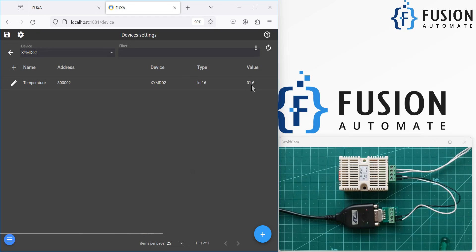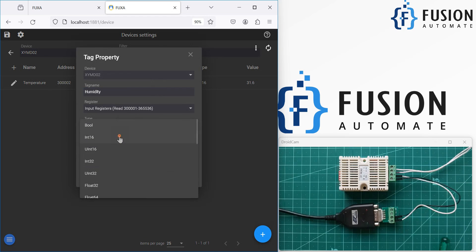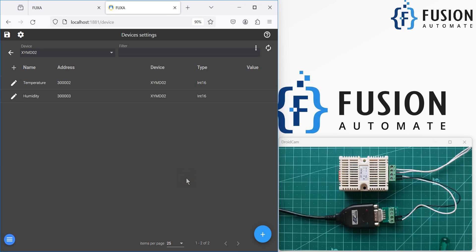You can see the value is 31.6, 31.5 — that is our temperature value. Now to add humidity, I click the plus icon, write the name 'humidity', the register is again Input Register, the type is Integer 16, and the address offset is 3 because we have humidity data from this XYMD02 sensor on Input Register 3. The divisor is again 10 because we divide the data by 10 to get the actual value. We press OK.